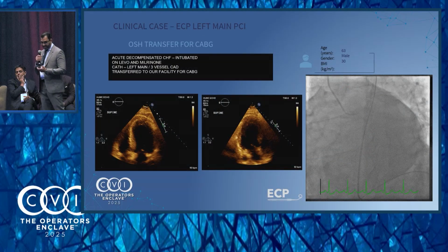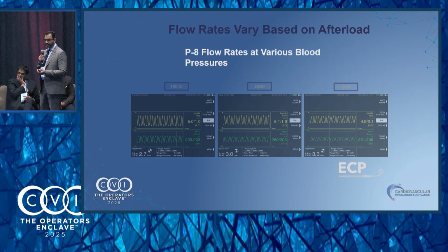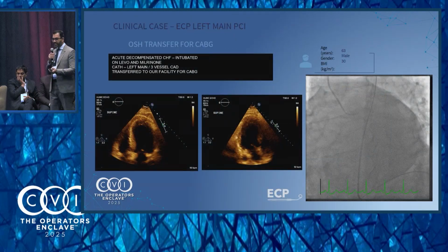The flow rates vary based on the afterload. It's a load-sensitive device. As you can see, at different pressures, the device can augment itself. And once you start using the device, you will learn that the afterload dictates the flow, and the pressure volume loops are slightly different for ECP versus CP.